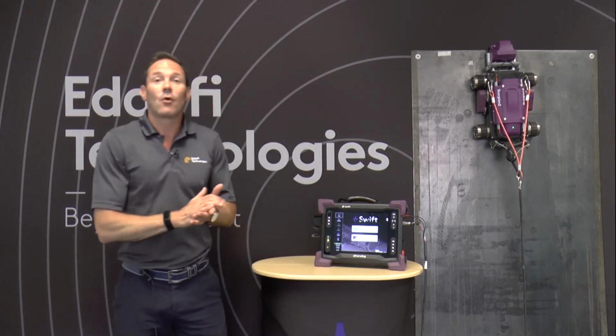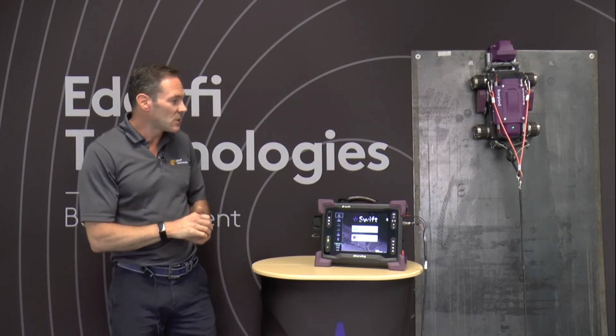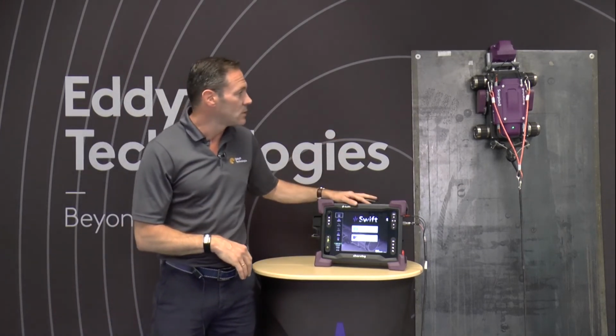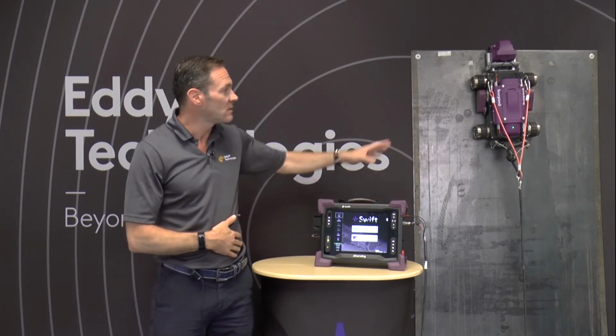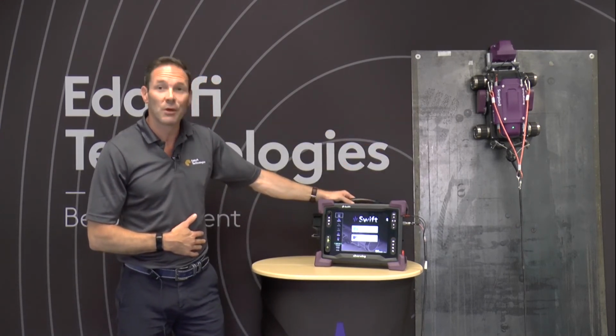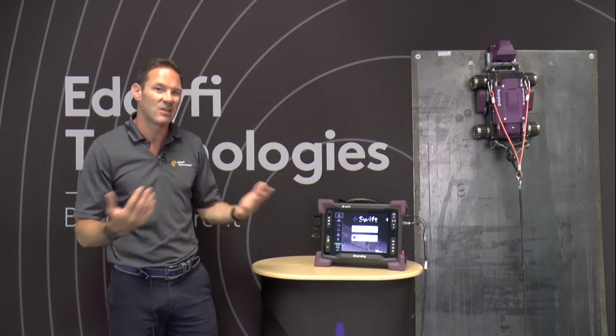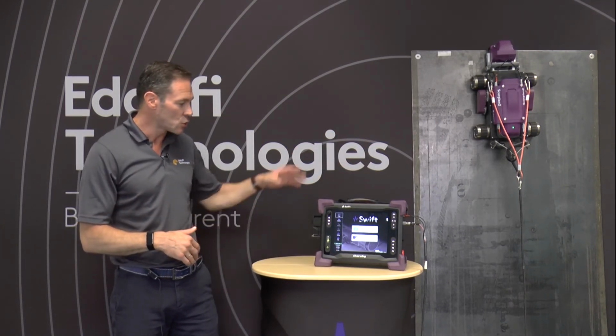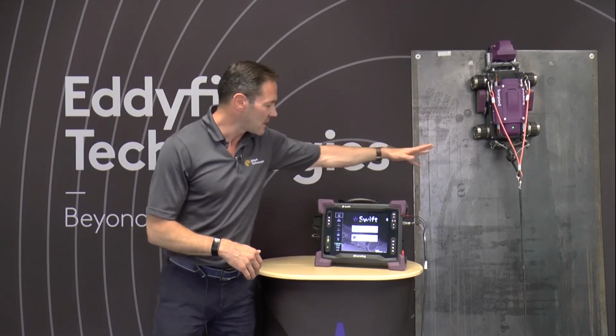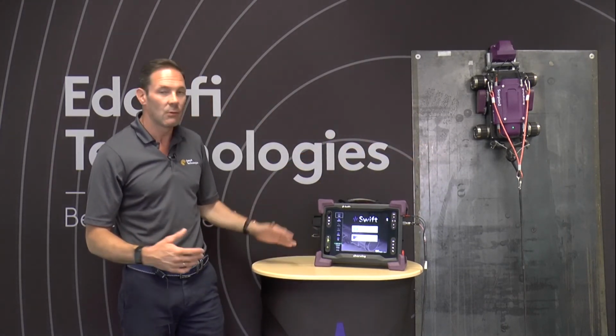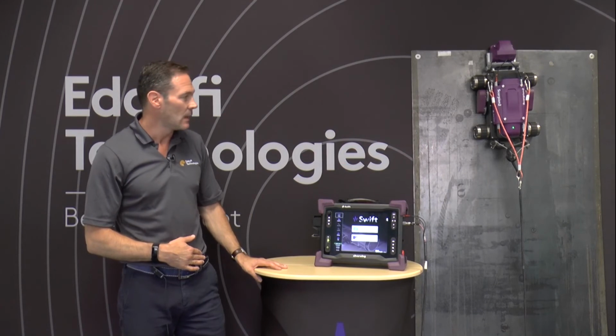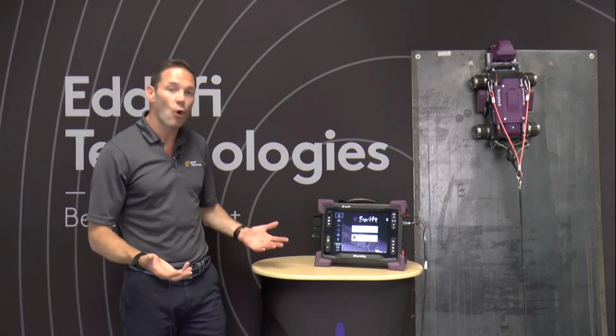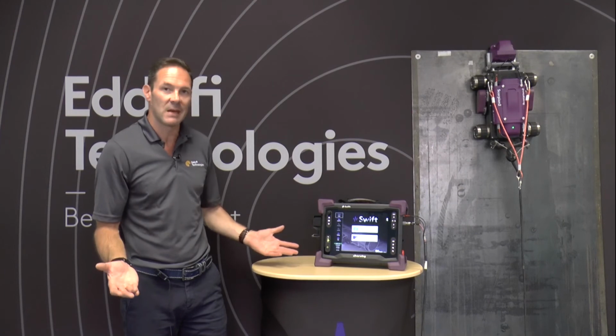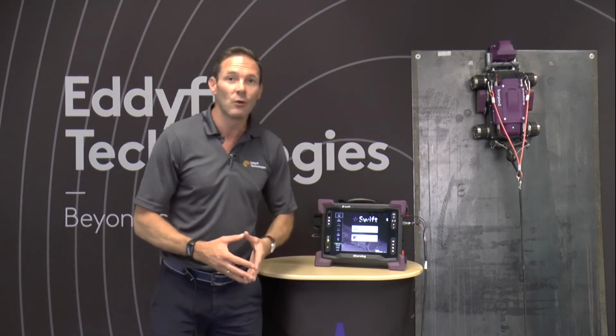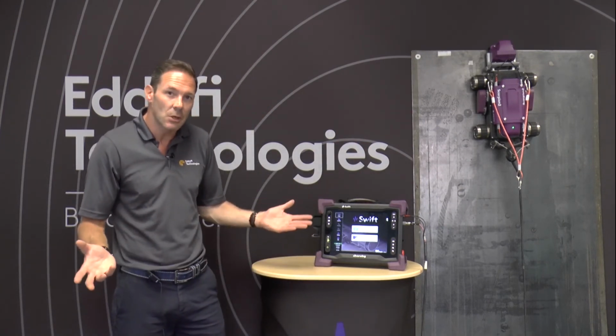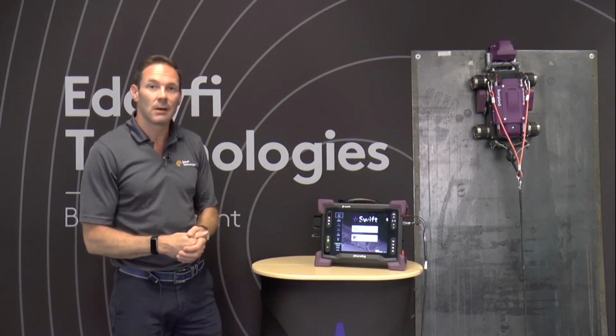Okay, and another question is, how quickly can the system be deployed in the field? Well, as you can see, we only have three components. We have the UT data acquisition unit, and we have the Scorpion crawler, connected with the reel. That's the only three components that we'll use. As soon as you turn the unit on, make the connections, switch it on, it will be powered on in less than a minute. The deployment of the system is literally a matter of minutes. There's no carrying of water because of the dry coupled wheel probe, and only 2 cases, so it's quite easy to actually deploy.